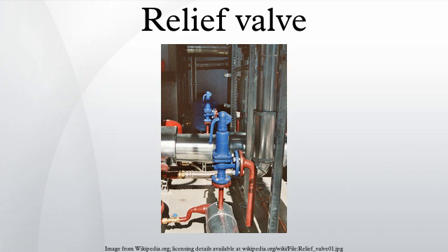In some cases, a so-called bypass valve acts as a relief valve by being used to return all or part of the fluid discharged by a pump or gas compressor back to either a storage reservoir or the inlet of the pump or gas compressor. This is done to protect the pump or gas compressor and any associated equipment from excessive pressure. The bypass valve and bypass path can be internal or external. Many fire engines have such relief valves to prevent the overpressurization of fire hoses.